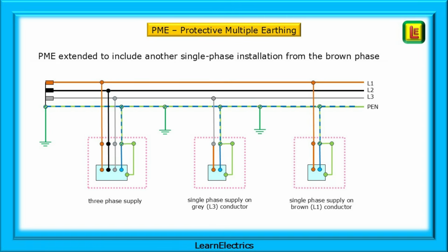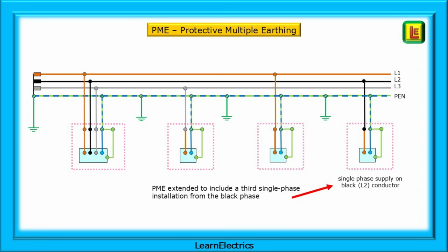An additional single-phase installation is shown at right and uses the brown L1 phase conductor. Any phase conductor will do, and most often the DNO will mix and match phase choices to best spread the load across the network. And another installation is added, this time onto the black or L2 phase. Within the limits of load and cable sizes, the PME can be extended as needed.